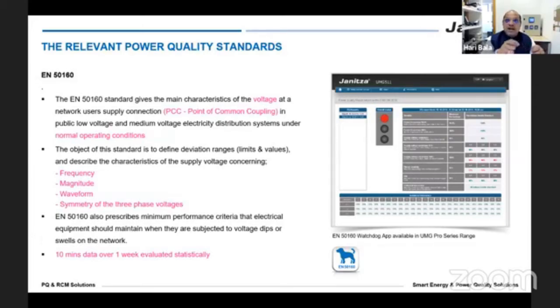So you cannot take a 1 day reading or a 10 minute reading and say that I'm complying to that particular standard. It has to be with respect to a period of time. So EN 50160 talks about generally 1 week of data being collected, and then it is done.